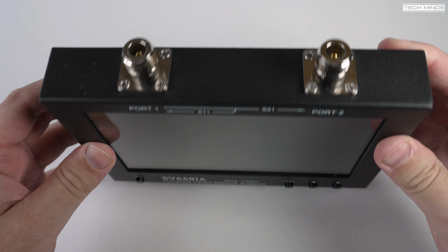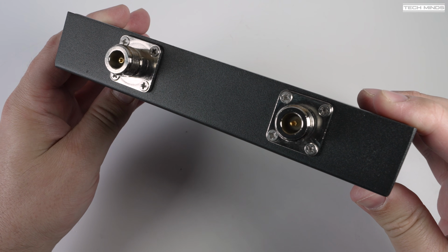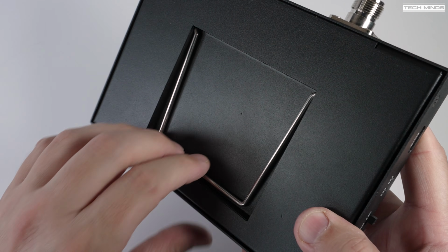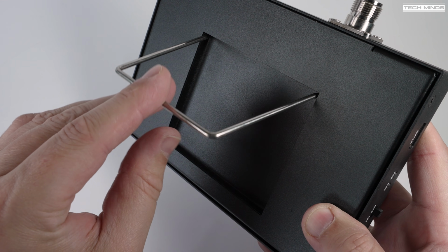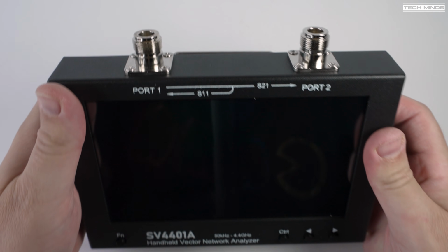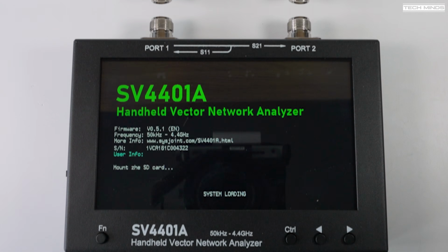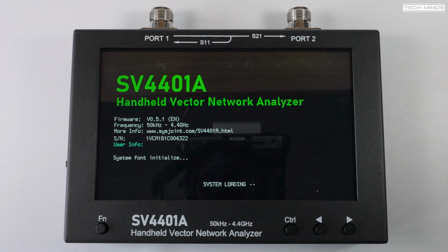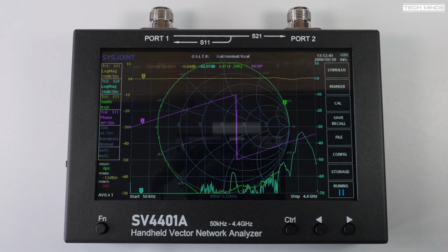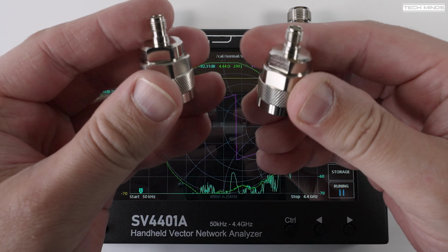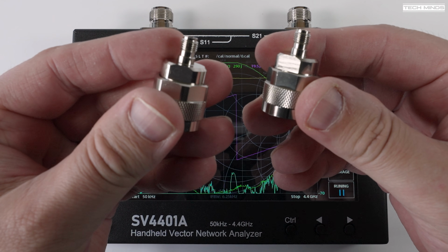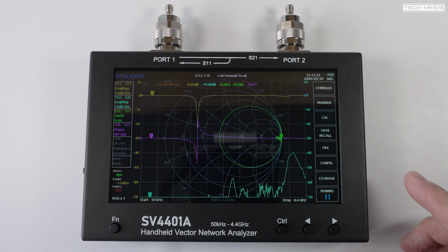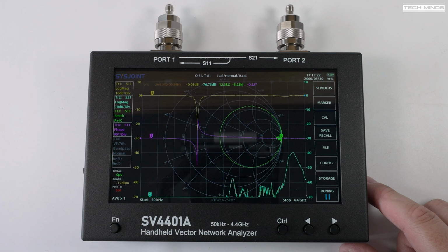The 2 port connections are located on the top of the unit, and on the rear there's this really handy pull-out stand, which makes the viewing angle perfect if you're going to be using this VNA on a desk or a flat surface. With the VNA turned on, I'm now going to attach the N-type to SMA adapters to port 1 and 2. Now we need to perform a calibration, so I'm going to calibrate it with the SMA patch cable attached to port 1, as I want the returned result to not include the cable.